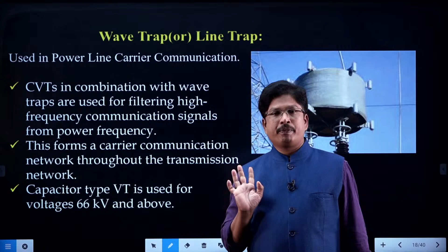and they may damage the substation equipment, these high frequency signals. To avoid that damage from high frequency signals, the element that you are going to use is the wave trap unit. It is going to filter out high frequency signals and it will normally allow power frequency signals. The wave trap unit or the line trap unit will normally allow power frequencies, but it won't allow the high frequency or carrier frequency signals easily. To filter them out, we are using the line trap unit or wave trap unit. Got it, right, students? That is the purpose of the line trap.